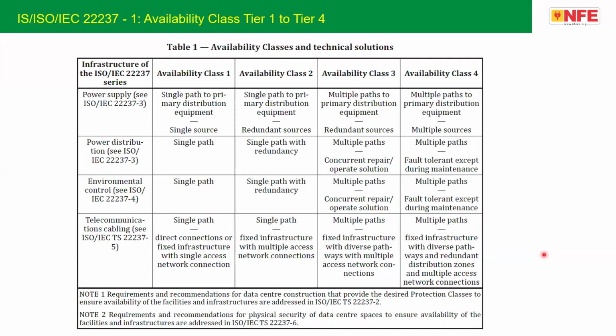Yeah, good morning, everybody. Thank you for this discussion. So, Mr. Gopakumar, it is very nicely presented here. I don't want to read everything, so from an experience point of view, without looking at the table, I may try to explain this. There are two institutes or organizations that maintain data center standards for tier class or availability class. One is TIA, which goes with the TIA 942 standard, and the other is the Uptime Institute. TIA says class 1, class 2, class 3, and class 4, whereas Uptime says tier 1, tier 2, tier 3, and tier 4.